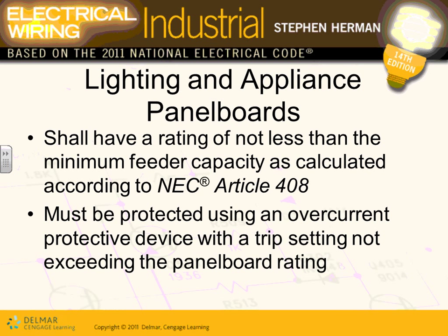This is very important, guys. It says the rating shall not be less than the minimum feeder capacity as calculated by 408. You guys already did that for me. Remember how we did the load calculation? When you came up with the amps for the lighting panel, first you calculated all the amps. That's the calculation based on 220 exactly. And your amps were, say, 120. Then you went to the next standard panel, 125.